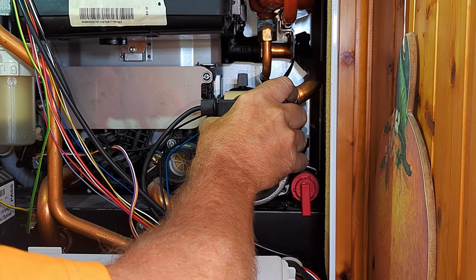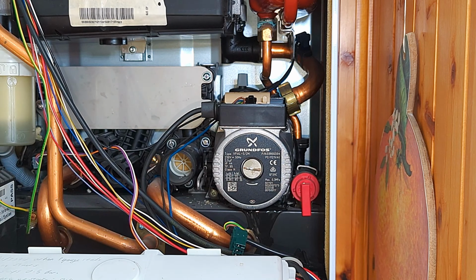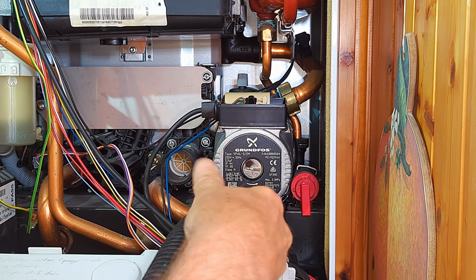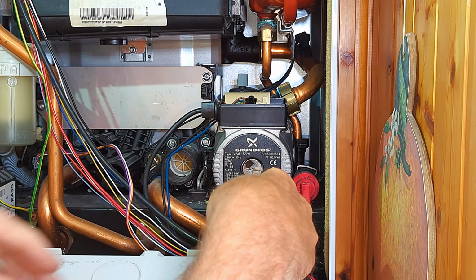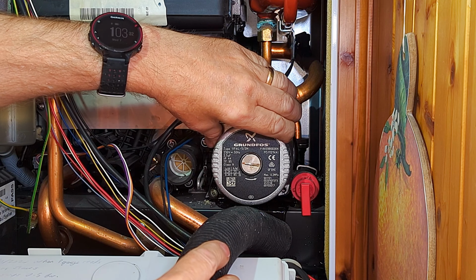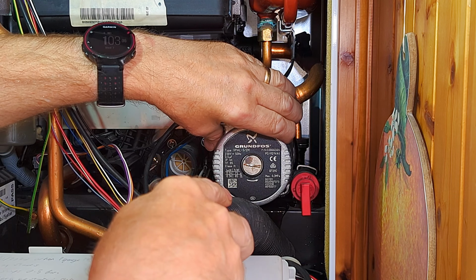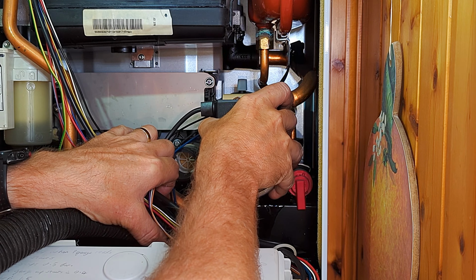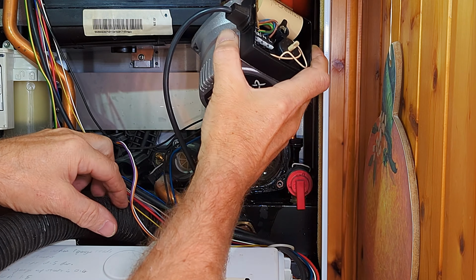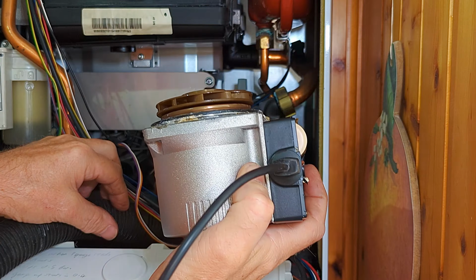Now I haven't taken out all the screws. Don't forget, when you wiggle the pump, you're going to get a whole lot of water come running out of your boiler. So once again, use my water vacuum, catching all that water that's coming out from the pump and the rest of the boiler. Once the water has stopped coming out of the pump housing, I can just lift away the pump like that.